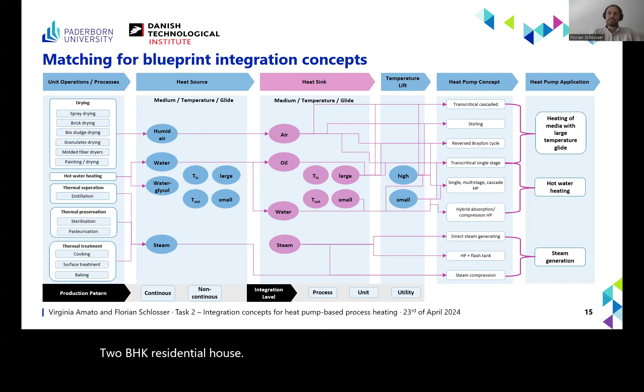On the other side, we have processes from thermal separation, preservation, and treatment, which can be supplied by steam generating heat pump concepts. Depending on the target temperature and whether vapor can be directly recompressed or other heat sources need to be used, the following heat pump concepts are available: direct steam generating heat pumps, if necessary with additional downstream steam compressors, heat pumps using a flash tank for steam generation, steam compression in combination with an evaporator, mechanical vapor compression, or in the end a combination of these concepts. Most of them we have already seen on the slides from Cordin in an application example, so I won't go into much more detail here.